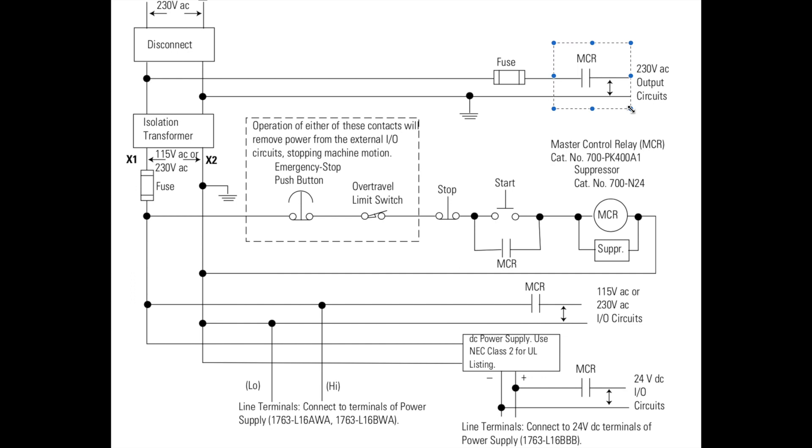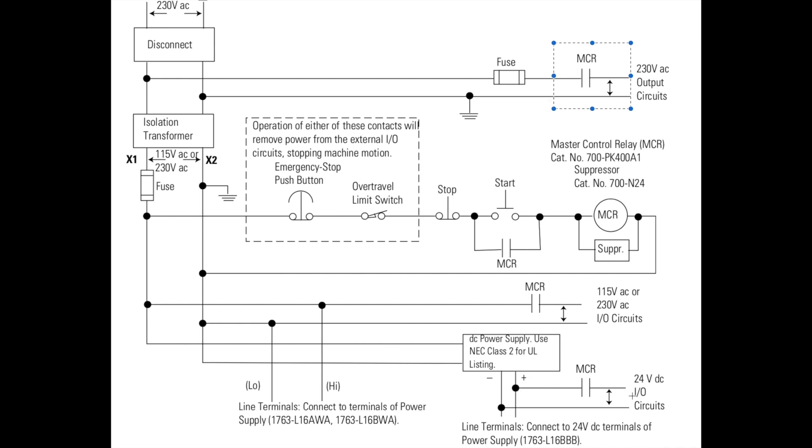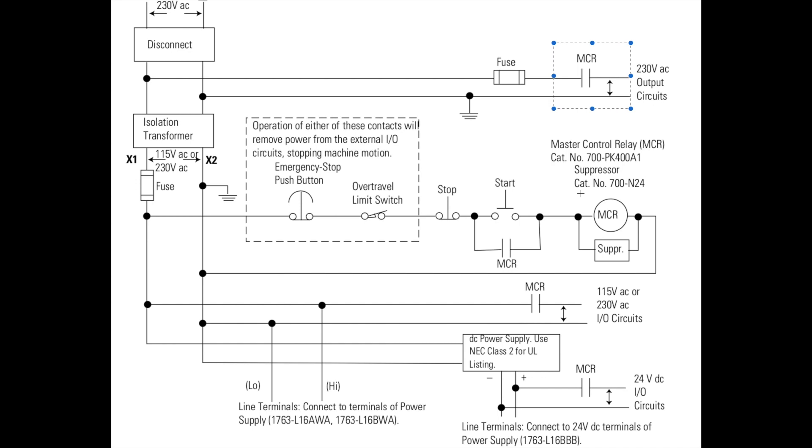What the relay is doing is if it's not energized, it's not making a connection through these electrical circuits. So it's killing the electrical circuit. If the e-stop gets pressed, the relay will become de-energized and will open all those circuits so that they do not operate.